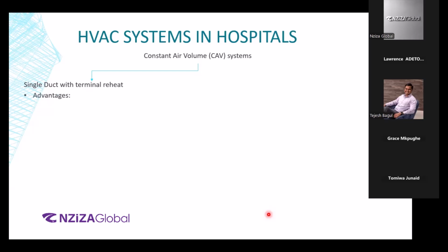Right? We'll talk about the advantages. So first of all, the HVAC equipment is centralized. You'll have one big mechanical room somewhere. You'll have one big duct serving all of the areas, concerned areas. So since you have one equipment that will be big enough, you're constrained with just one area that you need to worry about, and then that is basically the ease of maintenance that we are talking about. Since it is a central equipment, you can take advantage of the load diversity for optimal sizing. Basically, if you have just 3 operating theaters, 3 operating rooms in operation out of the 10, you need to run the AC, the air handling unit just to serve those 3, not all 10.